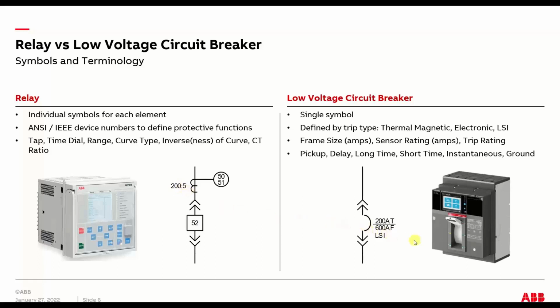And then the equivalent for a low voltage circuit breaker is its trip characteristics. In this case, it's electronics, so it's LSI: long, short, instantaneous, and then its sensor and frame ratio, 200 amp trip or 200 amp sensor plug, and then 600 amp frame. The LSI would roughly equal, the LS would be the 50. I'm sorry, the LS would be the 51 device, and the I, or instantaneous, would be the 50. So 50 is instantaneous, 51 is time overcurrent.